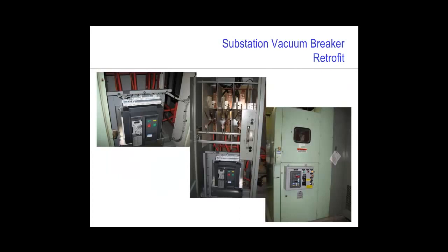What we've shown here is pictures from the actual installation. On the left is the new vacuum circuit breaker installed, showing the secondary control terminations. In the center is a picture of the breaker and the existing load break switch, and on the right is a picture of the assembly with the door closed. Note that there's a control box on the front of this assembly that was a part of this retrofit that includes the 50/51 device protecting the primary bus, and also a breaker control switch, the lockout relay, breaker indicating lights, and also a switch and lights for the ARMS system.